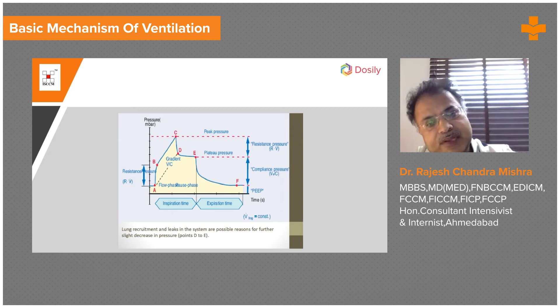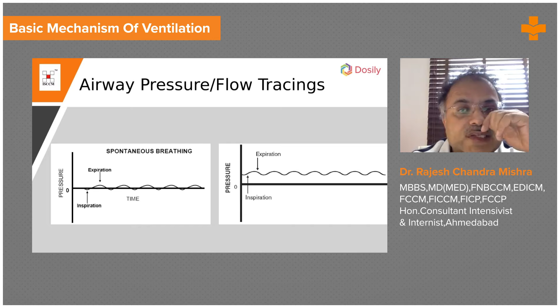As I told you, if you are breathing, this is the inspiratory trigger, this is the limit you decide, and this is all a sinusoidal curve. If you see on a baseline this kind of breathing, very classical, you are breathing on your own without a ventilator. But if you see the same breathing with a baseline FRC here, and at a certain pressure, which classically a CPAP machine does, where you increase the intrathoracic pressure to a certain level and the patient ventilates on that, which is classically applied particularly in LVF patients, then it's called CPAP mode.